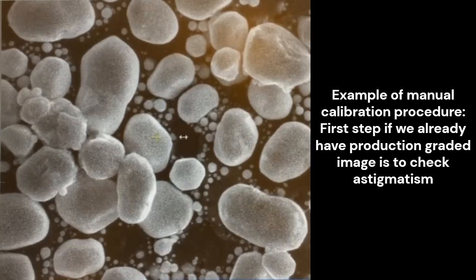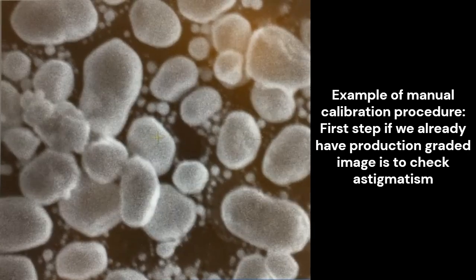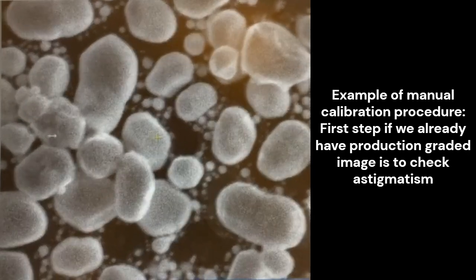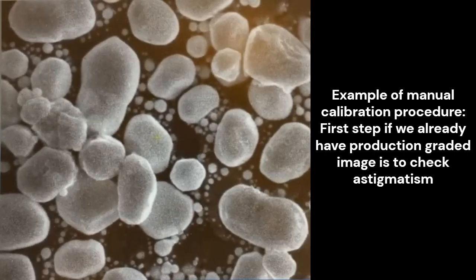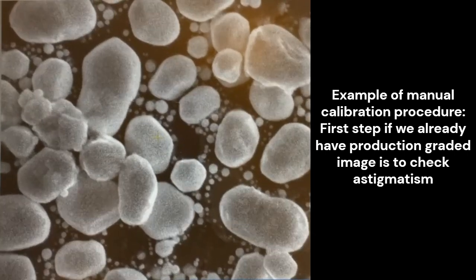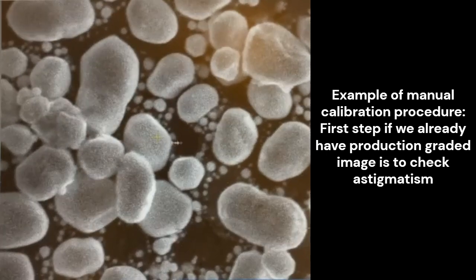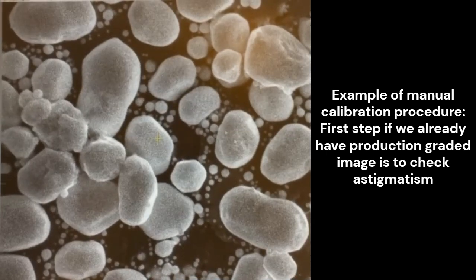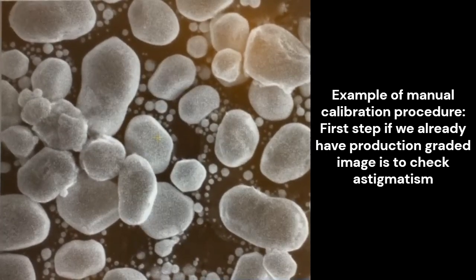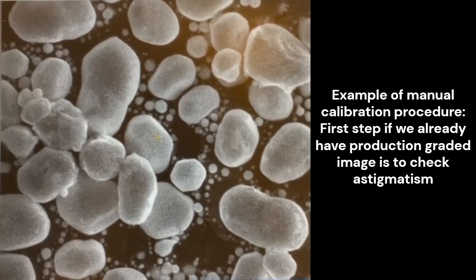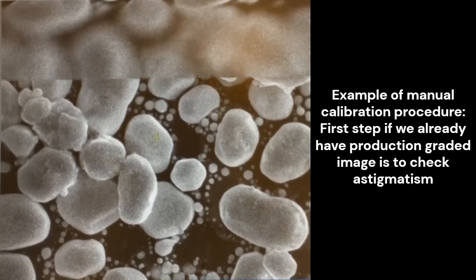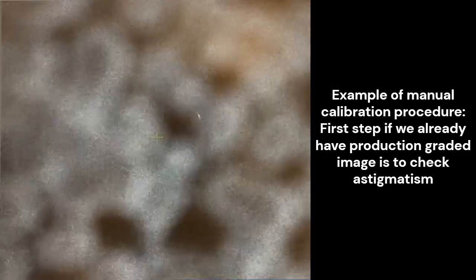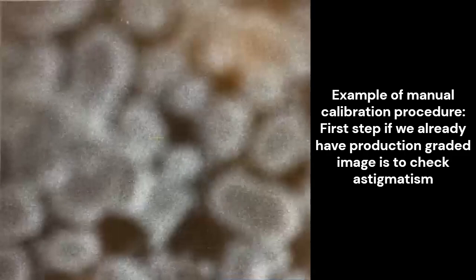Now to evaluate astigmatism, again, focus. As I focus to the right and to the left, I don't see any stretching anymore, but what I do see is a shifting of the image. You can see it's kind of shifting along this diagonal, and when I see shifting, I want to adjust the lens alignment. To do that, I'll click the modulator, and I want to go to a shorter dwell time so we can visualize the oscillation.